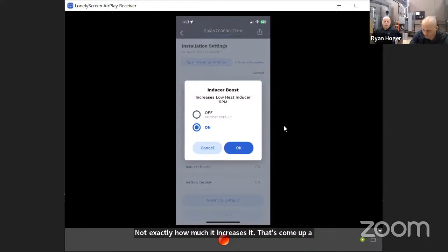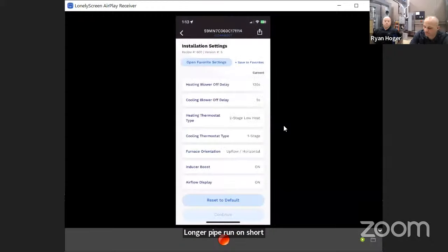I don't remember them listing it specifically, but a lot of guys just tend to turn that on. It seems like for a normal install with the furnace sitting there and 10 or 15 feet of pipe going to the sidewall, you probably don't need this. But the longer the pipe run gets for the venting, the more likely you'll want to run at a higher RPM. It's a little more noise and energy, but if that's what it takes to get the air out of the pipe, so be it. So without specific data, you're kind of guessing based on your gut on each job—longer pipe run on, shorter pipe run off, and everything else in between.